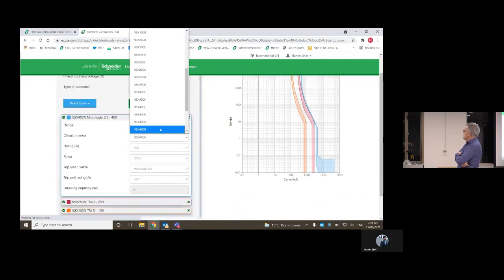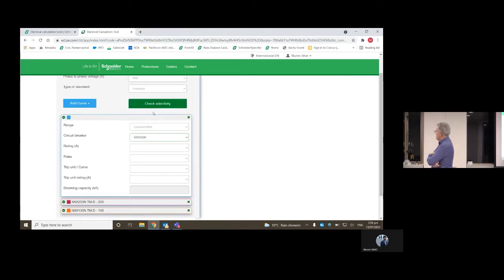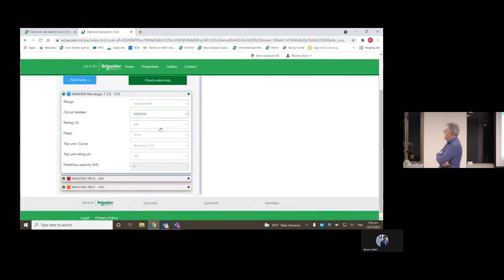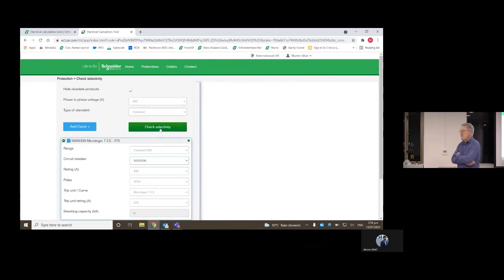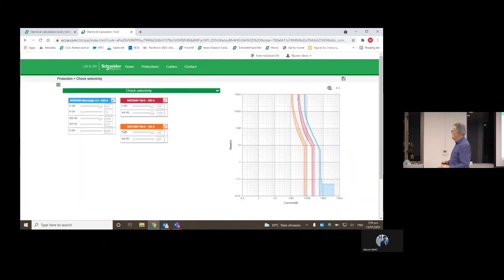In this situation, I'm advocating, just through general knowledge, to change it to a 630. But the reality is, because it's the same frame size, it's a great thing. If it's physically the same frame size, we can slot it in the same place. With a 630, we can still adjust it to the 400 or less than 400 to what we need in terms of our IR setting. Yes, it costs us a bit more, but look what we've achieved.